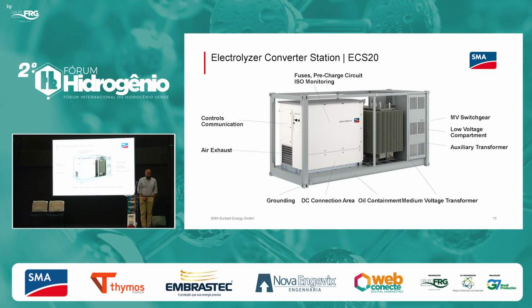What kind of solutions do we provide? As I said, we mainly see big systems growing very fast, not small systems, so I'm focused on megawatt-scale projects. This is a solution based on a 20-foot container: a rectifier unit, a transformer to the medium voltage connection, your switch gear, and your DC connection—meaning you can place this block in the middle of your plant, with the AC connection problem solved directly.